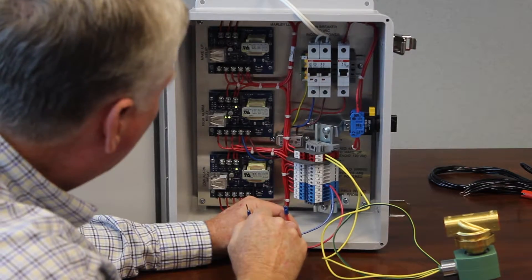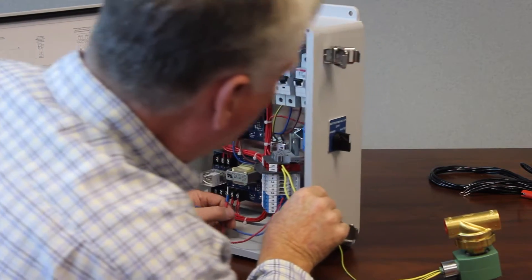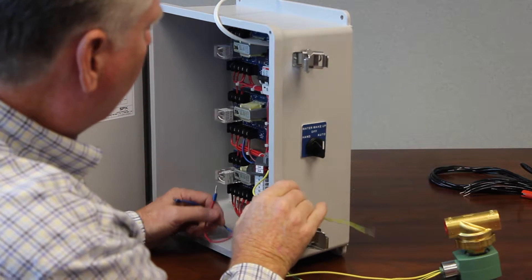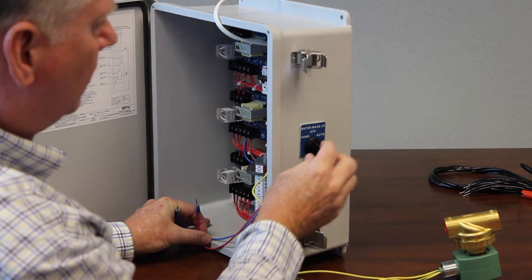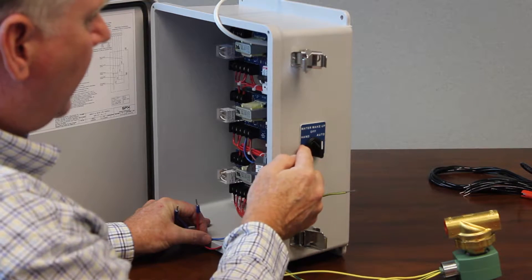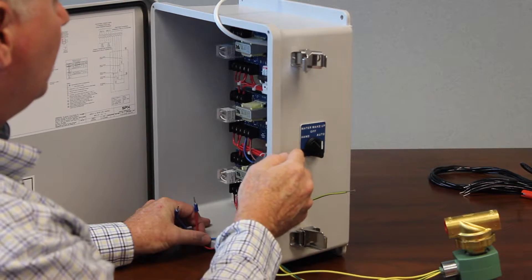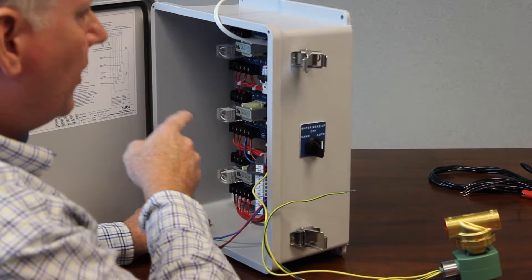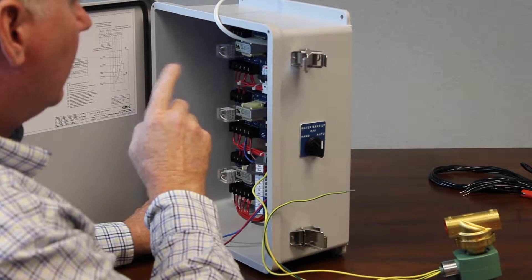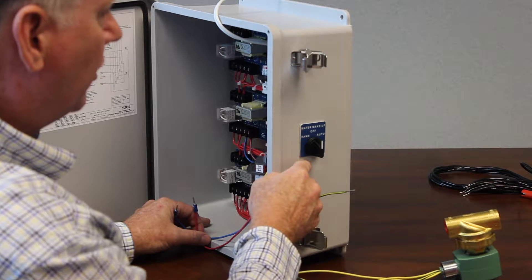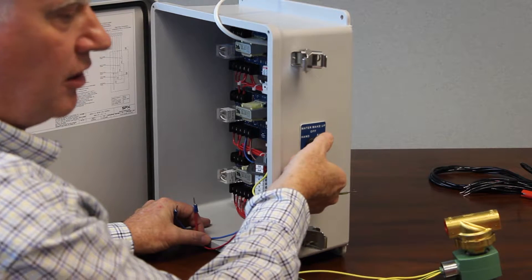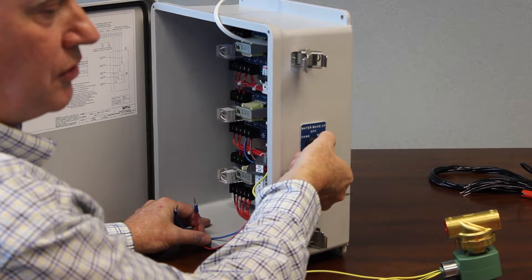So we got power to everything. My switch is in the off position. The first thing I'm going to do is I'm just going to throw this to hand. And when I throw this to hand, we bypass the circuit card that's in here, and we directly apply 120 volt power right to the solenoid using this switch. So when I put this in hand, it should come on. So you should hear this.